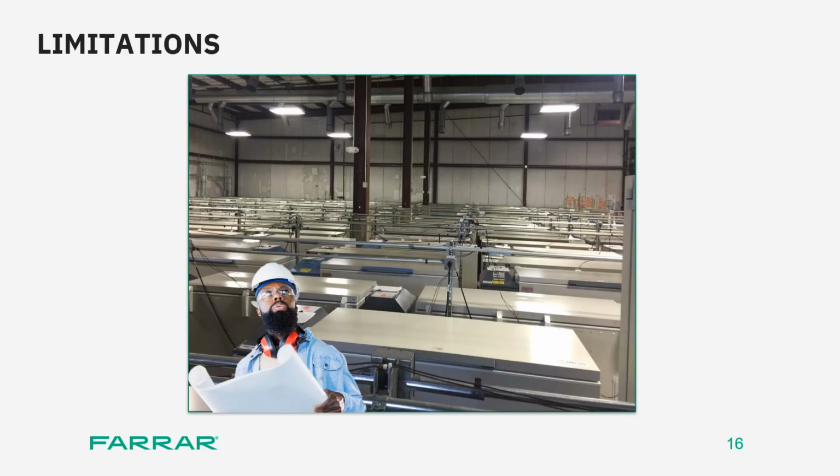Now, increasing the building HVAC can be done. However, it's a pretty large undertaking. So to do this in another fashion, we can reduce the load and reject heat by refrigerating the surrounding space. By doing so, the additional equipment can drive a lower temperature delta, leading to faster recovery. That means less wear on your freezer equipment and less worry down the road.